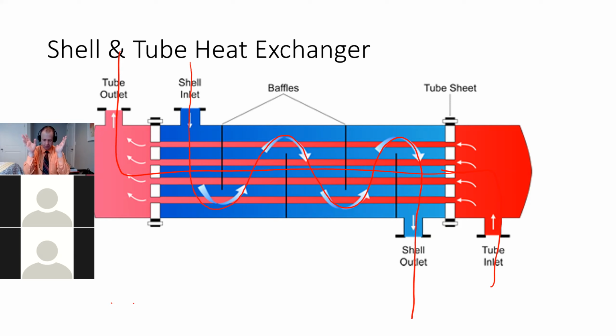So are tube companies different from shell companies? No, usually the same company sells the whole thing. We'll talk in a couple days about different types of shell and tube exchangers. This one has what's called a fixed tube bundle, welded onto the shell, so I can't take it out. Some designs let you pull the whole tube bundle out so you can clean the outside of the tubes, the shell, and the inside of the tubes. I'll show you pictures of that in a couple days.